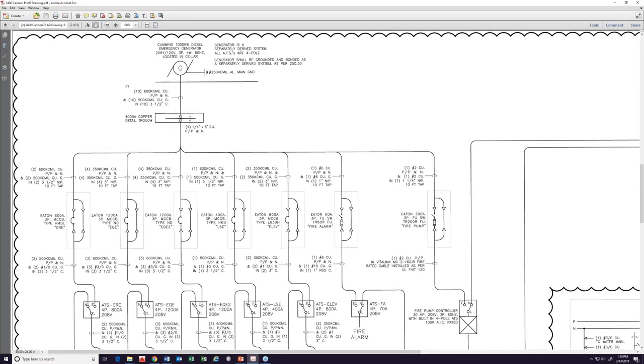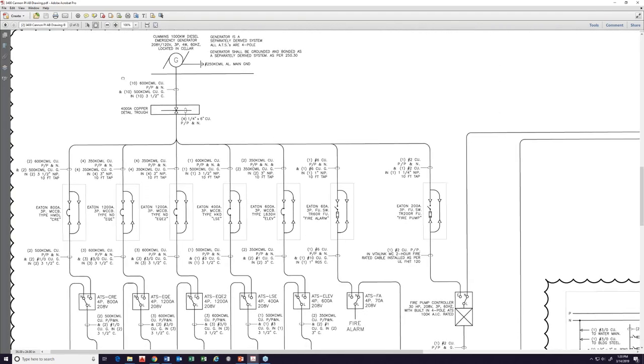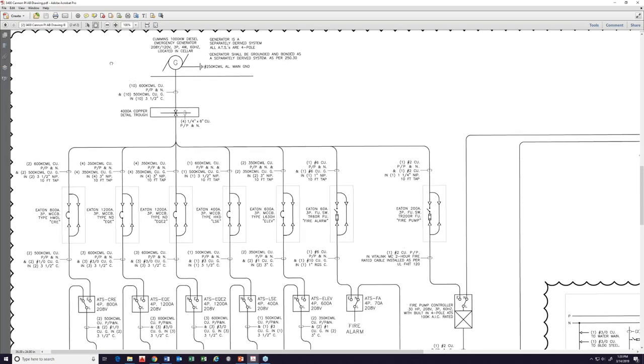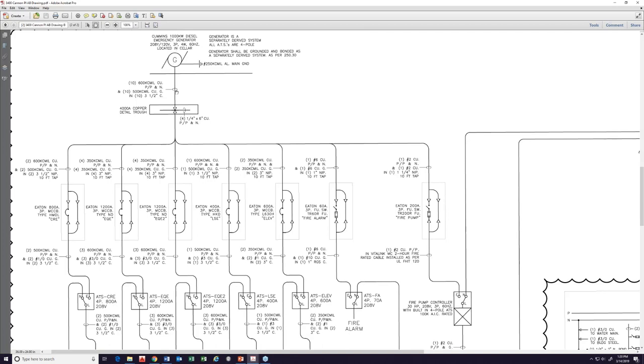Now, when we're talking about an emergency system, there's something very fundamentally different, because an emergency generator, regardless of how good the generator is, a 1 megawatt, you're not going to get too much available fault current out of this. And it's considerably weaker than the utility source. So you have to look at the devices in a completely different way. And this is where the challenge comes in. When you're looking at this particular design, this is actually a trick I learned from Charles Pratt, and I love this idea. Contrary to popular belief, emergency generators do not need main breakers, although every generator vendor is going to try to sell you the breaker because they love to make money, don't we all? But you don't need that breaker in there. That breaker is not protecting the generator. It is only protecting the downstream feeders. And I don't need that.